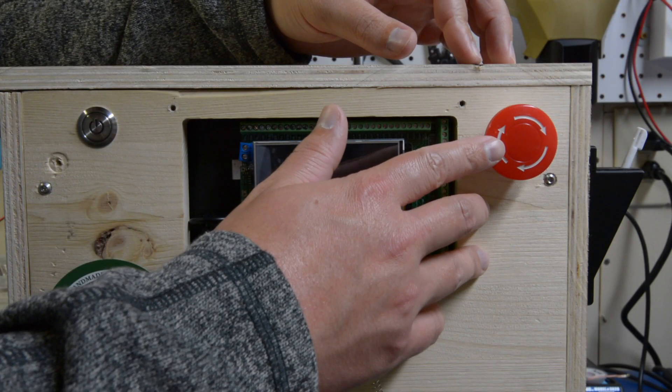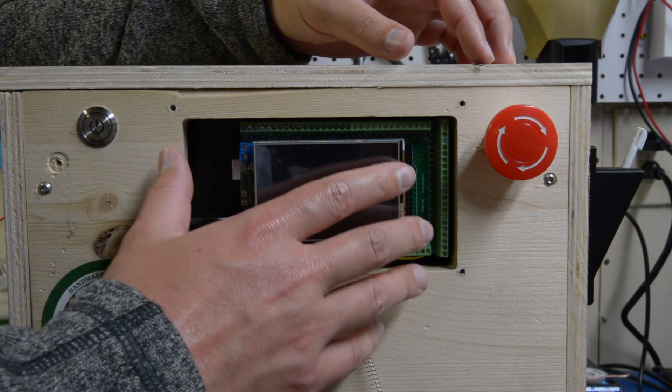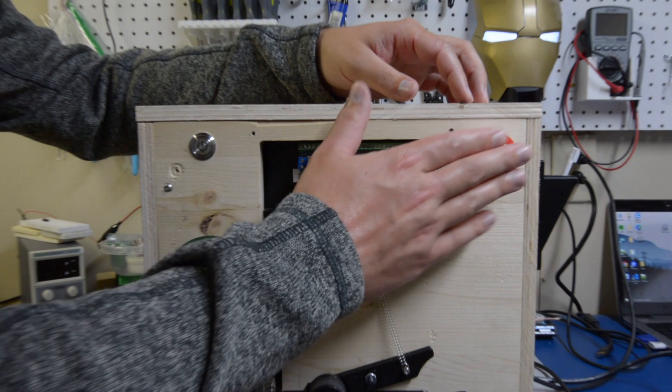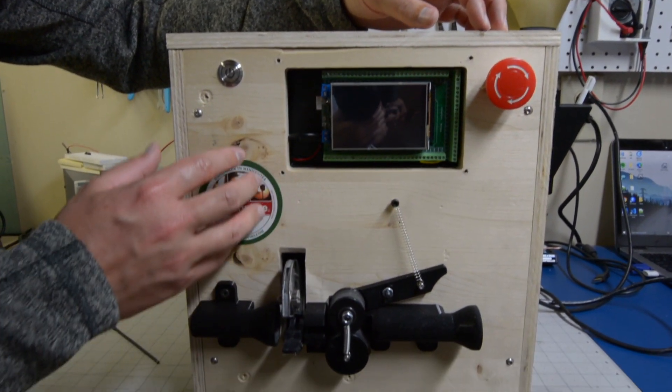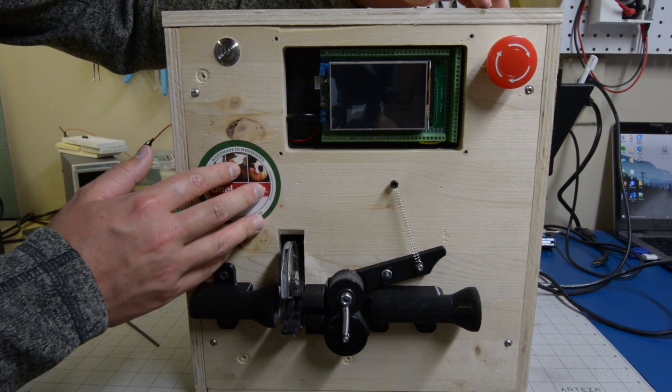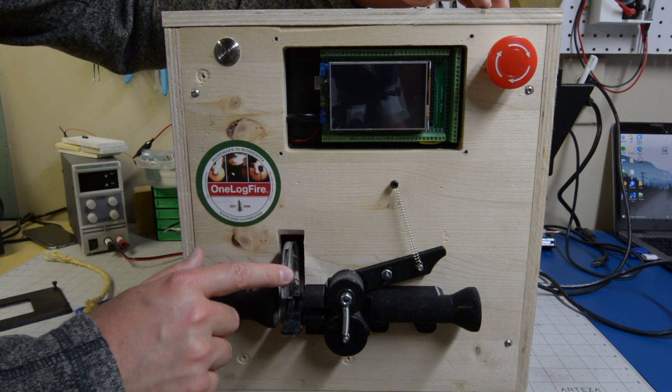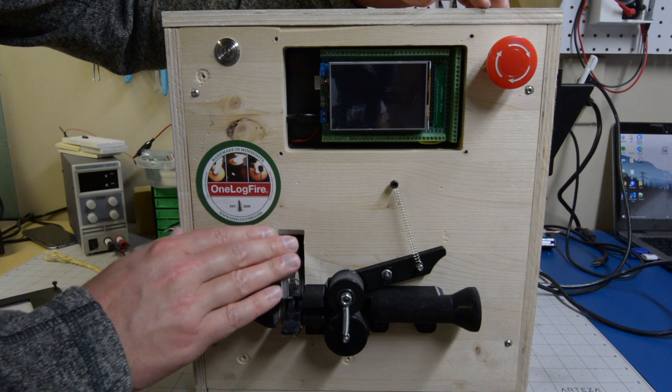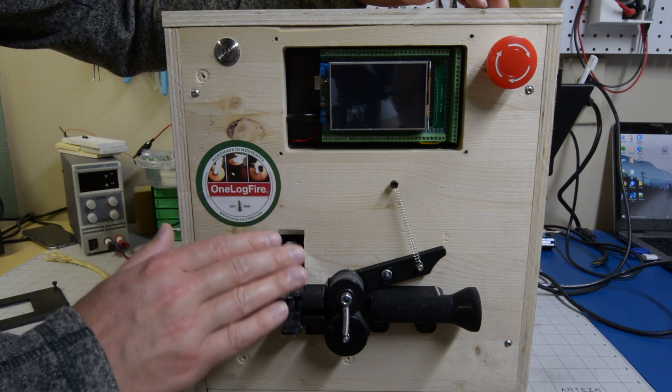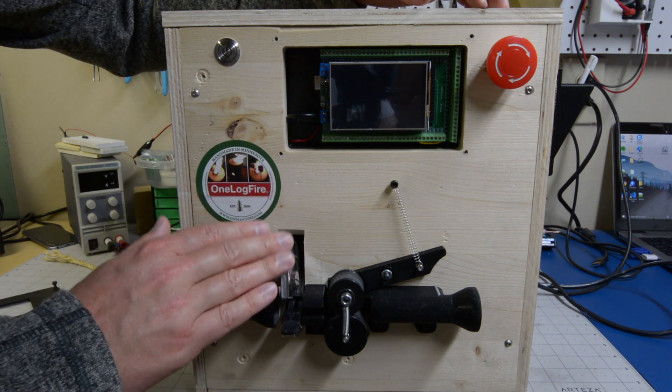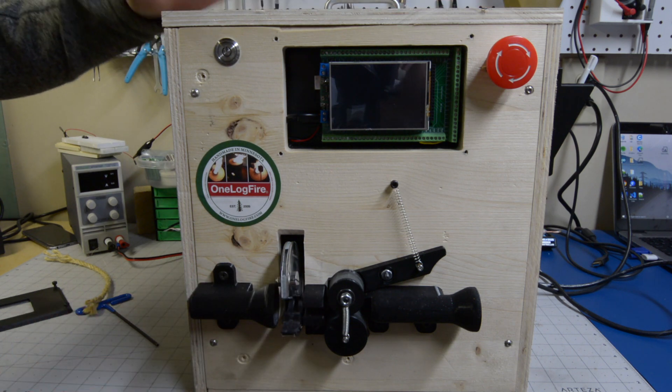Right here we've got our emergency kill switch which kills all power to the microcontroller and touch screen display. When it's pressed, it kills all power and only relays power to our linear actuator driver. The reason for this is we didn't want any software involved and it's very reliable knowing it's only hardware in case of an emergency. So now we will take off this housing and show you the back.